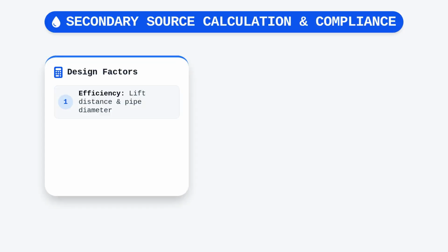The capacity of these secondary sources must be calculated with extreme care, particularly regarding drafting operations where the lift distance and pipe diameter significantly restrict efficiency. You must ensure that these tanks are sized to support the full duration of a fire event while accounting for factors like evaporation and the minimum water level requirements for vortex prevention.